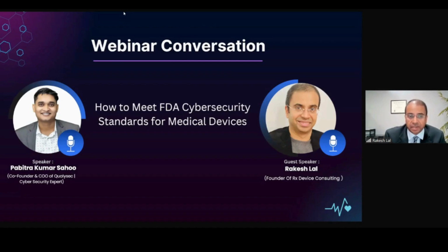In a 510(k) submission, FDA will expect a full risk management report that details threat modeling assessments and vulnerability identifications. You need to evaluate and monitor various databases that describe the threats, including NIST and so forth. They will expect a fully defined software bill of materials that explains all of the software components and information about them. The risk management report would likely include pen testing. If vulnerabilities are detected during pen testing, they would expect mitigation and retesting, and potentially a letter of attestation from a third party.